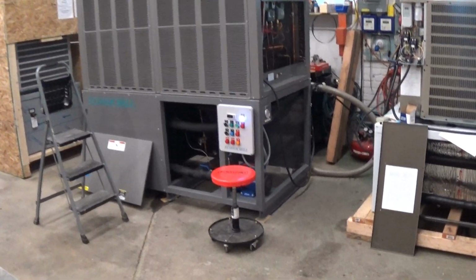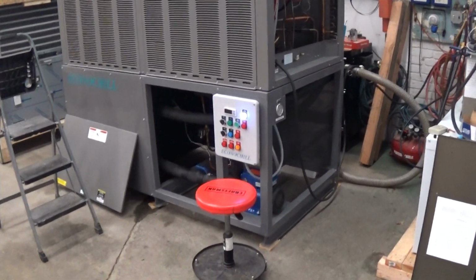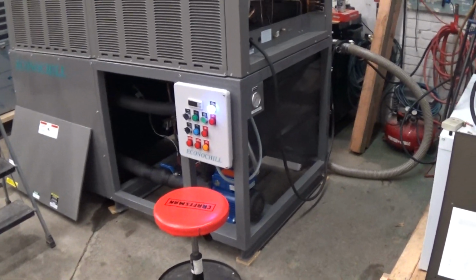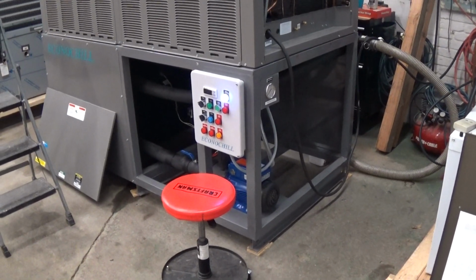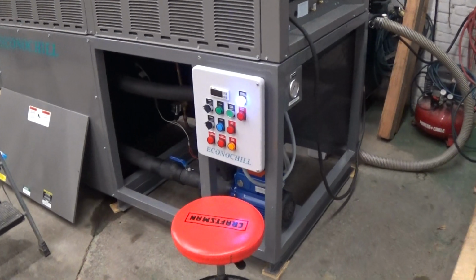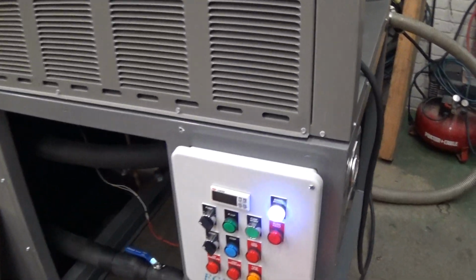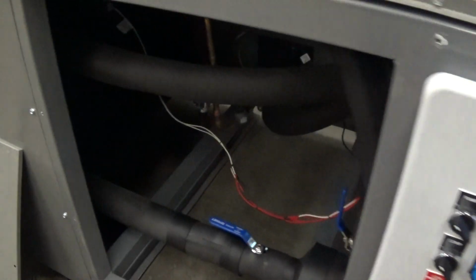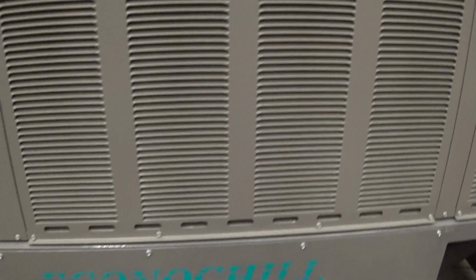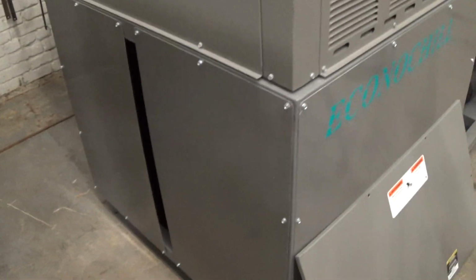So again, we got some covers off here. This is a 10-ton, 230 volt air-cooled Glycol chiller. We're just going to start going over some components and construction of the unit. Underneath here we have our insulated Glycol reservoir in the corner of the tank. For a 10-ton, we actually have a nice sized, about 72 gallons. On this side here, you can see there's a Glycol sight glass, which is nice.